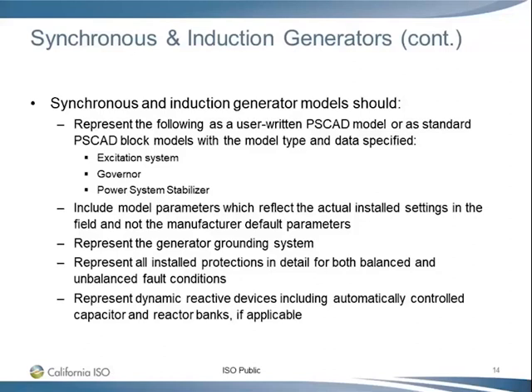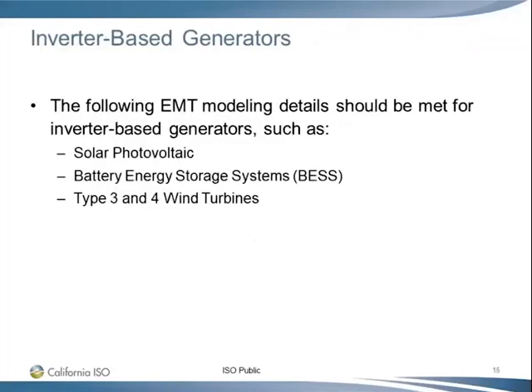And you should include model parameters that reflect actual installed settings in the field and not the manufacturer default parameters. So this is true for everything we are talking about here. We'll repeat that again and again. And you will represent the generator grounding system, represent all protections, and represent the dynamic devices in the plant. Next slide, please.